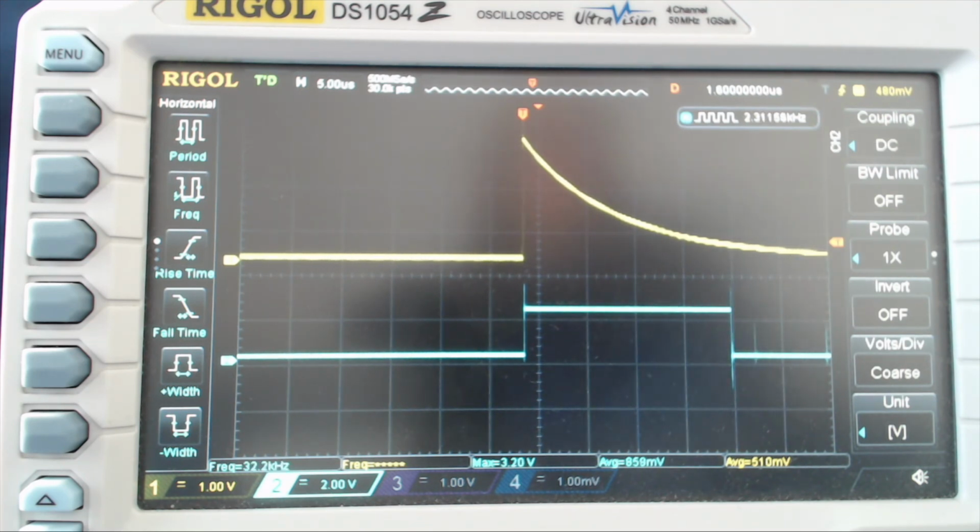The discriminated signal becomes longer because we are reducing the threshold. If we reduce again to 2400, longer again. If we make it higher, 3300, it becomes shorter, 4000, shorter again.